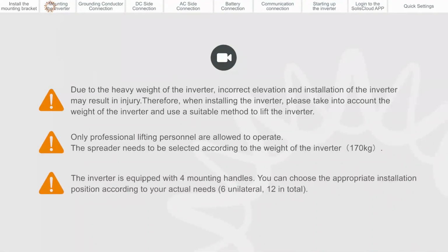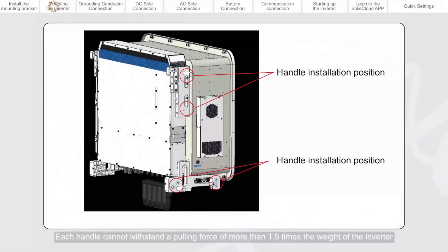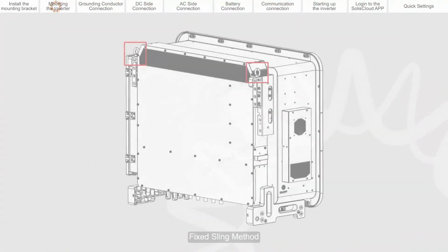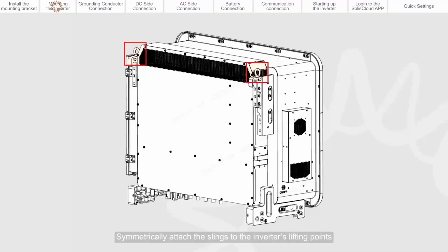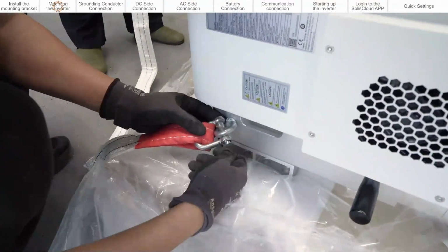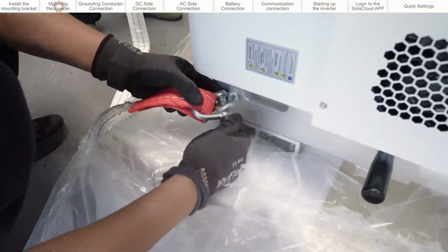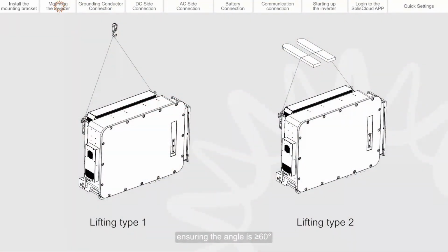The inverter is equipped with 4 mounting handles. You can choose the appropriate installation position according to your actual needs, 6 unilateral, 12 in total. Each handle cannot withstand a pulling force of more than 1.5 times the weight of the inverter. Fixed sling method. Symmetrically attach the slings to the inverter's lifting points, ensuring the angle is greater than or equal to 60.